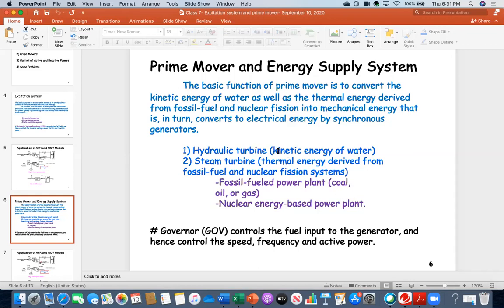In case of hydraulic turbine, it controls the falling of water. This means it controls the amount of kinetic energy. There is a control system with the valve opening and closing. So therefore, see, the governor controls the fuel input to the generator and hence controls the speed, hence frequency, and hence active power. So these three terms are interrelated: speed, frequency, active power.